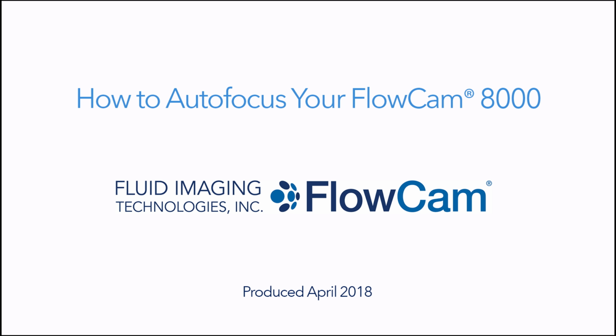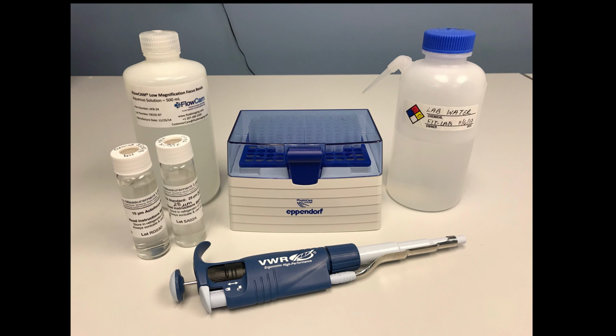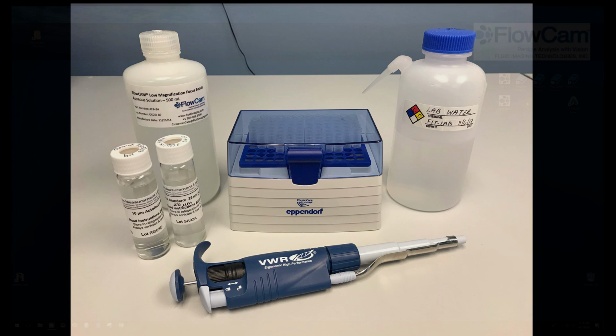In this training video, we will demonstrate how to properly focus your system using the autofocus procedure. You will need the following materials: your flow cell, focus solution beads, rinse water, pipette, and pipette tips. Depending on your objective piece, you can use AFB 1020 autofocus beads for 10 and 20x magnifications, and AFB 24 for the 4x magnification. We also offer a 10 micron size focus bead solution upon request.